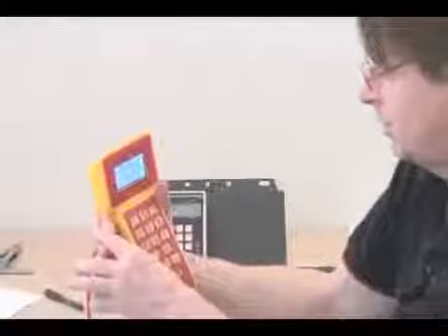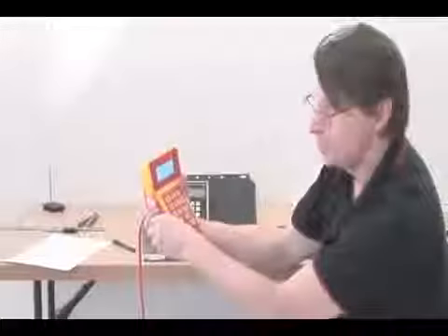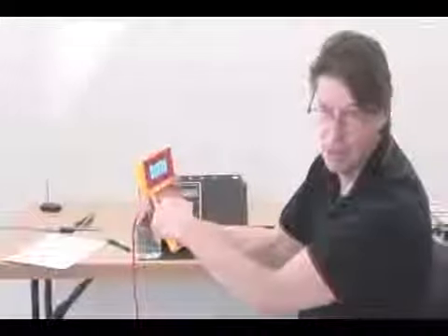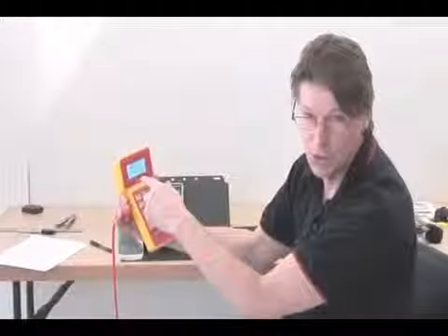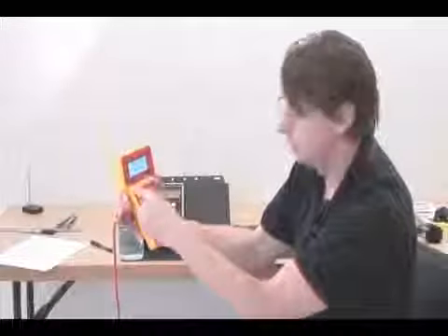So that's critical. The other thing that can happen is if our tube is pinched and we plug it into the gauge, that right away we'll see a big positive pressure. And if we see that, we know we have a pinched tube problem.